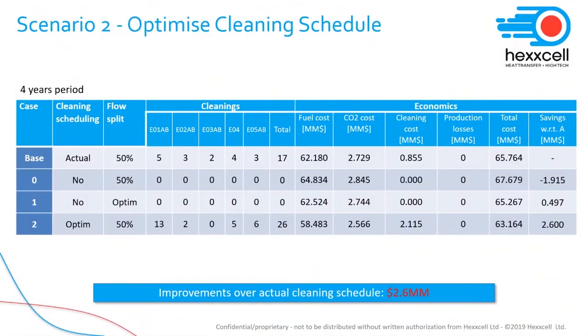This optimization led to identifying over $2.6 million additional savings on top of the $2 million already obtained by the refinery. This was the result of a combination of an increased number of more targeted cleaning actions, i.e. more frequent cleanings of E01, which led to an increased cost of cleaning, more than twice as much, but to a significant reduction of fuel and CO2 emissions. However, this only considered the optimization of the cleaning schedule at a fixed flow split.